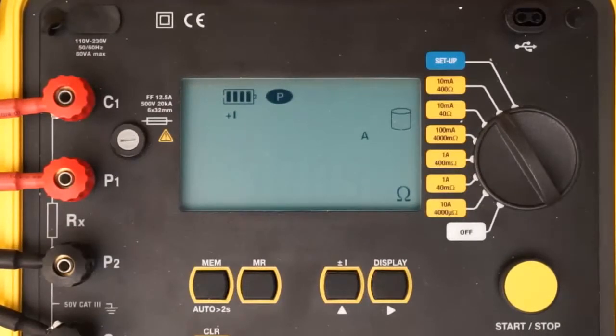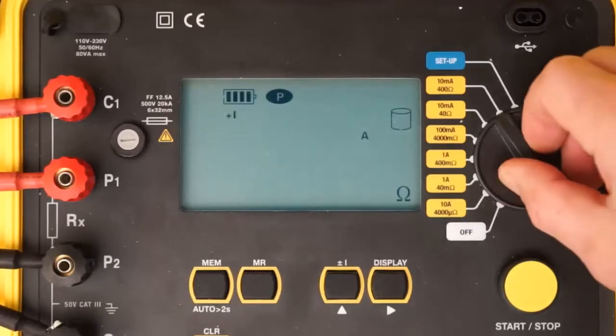If the resistance you are testing is unknown, we suggest starting with the instrument's highest resistance range and then lowering the range until you obtain meaningful results. In our demonstration, we are using a shunt of known resistance, so we will turn the dial to the 10 amp, 4000 micro-ohm setting.